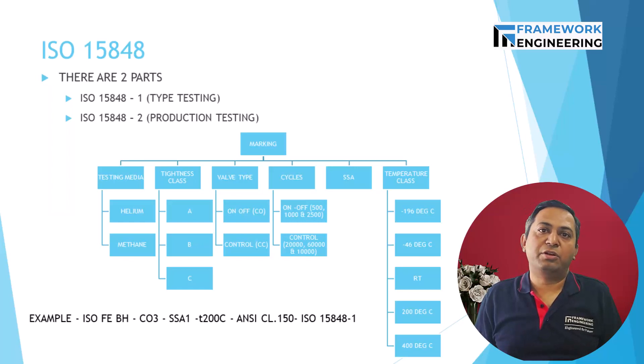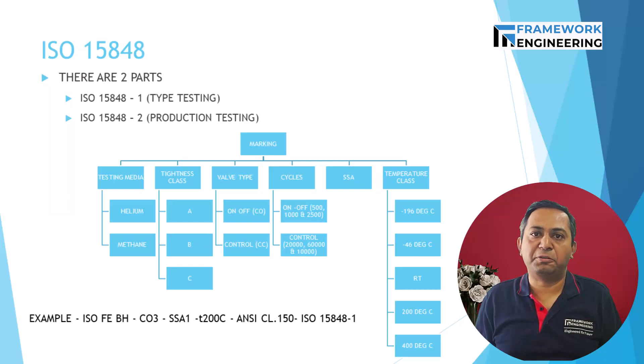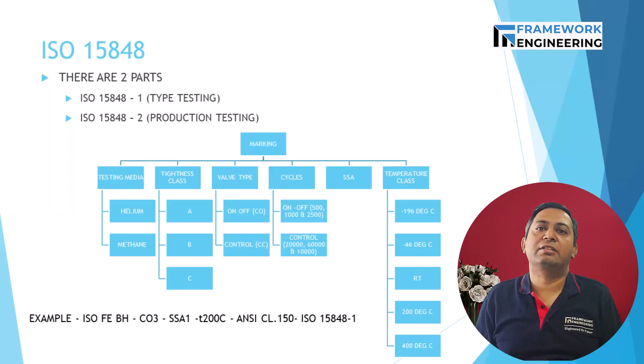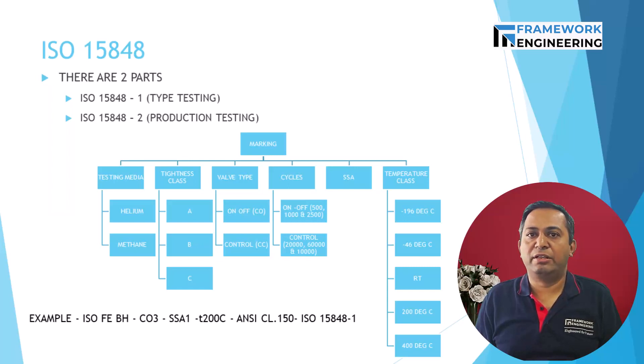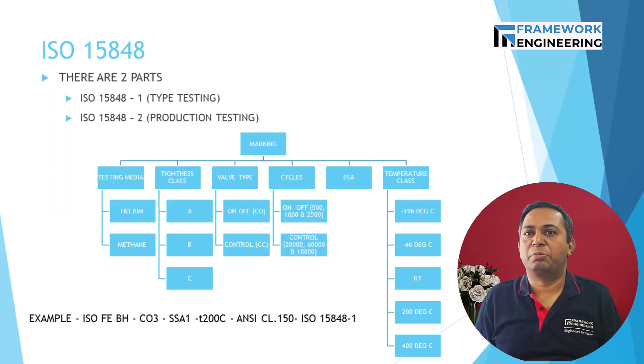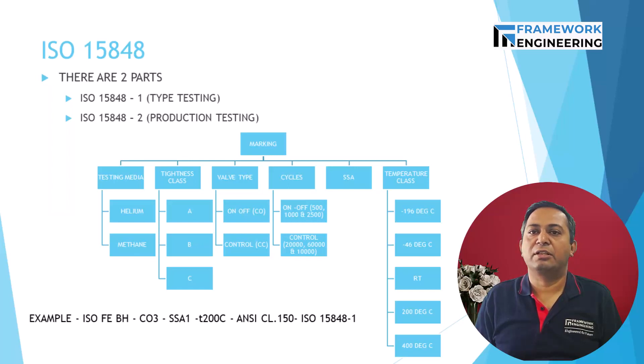Part 1 defines the requirements for fugitive emissions as shown in the table. Testing media can be either helium or methane. There are three tightness classes defined: A, B, and C. Class A refers to a leakage rate of 10 raised to minus 6 milligram per second per meter. Class B refers to leakage between 10 raised to minus 6 and 10 raised to minus 4. Class C refers to leakage between 10 raised to minus 4 and 10 raised to minus 2.